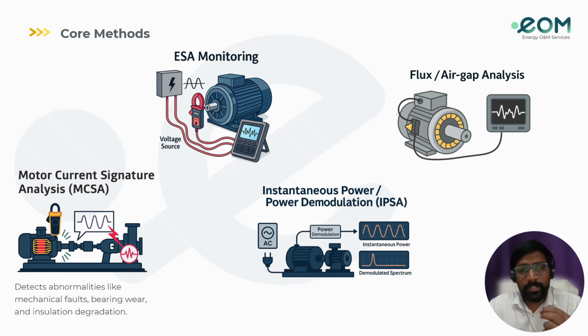Coming to the second one, which is voltage signature analysis, it is very useful for supply problems and to correlate with the current, that is, the power quality impact. Although the signal is obtained from the motor's voltage source, voltage signature analysis is quite similar to motor current signature analysis. In the case of motors, it can be used for examining stator electrical imbalance and identifying problems caused by motor power. The analysis of the manufacturing unit is where this method is most frequently applied.